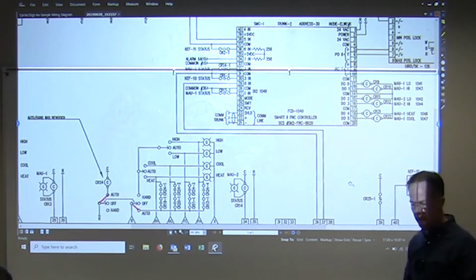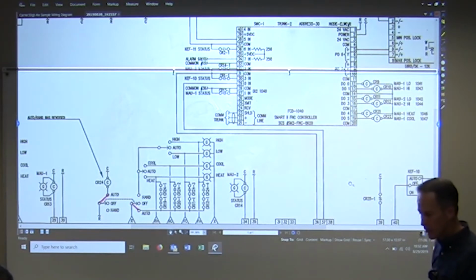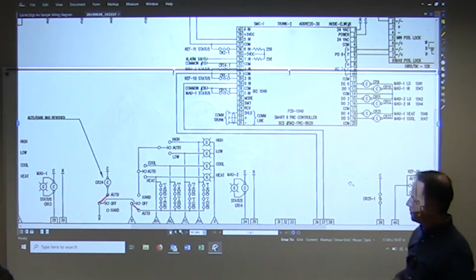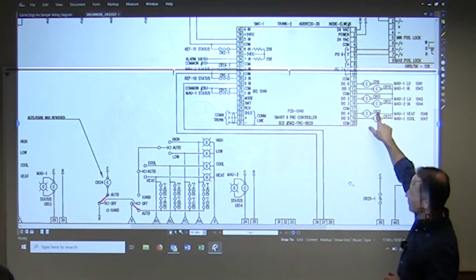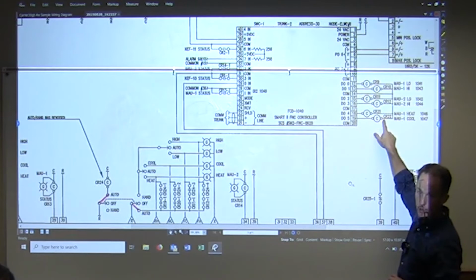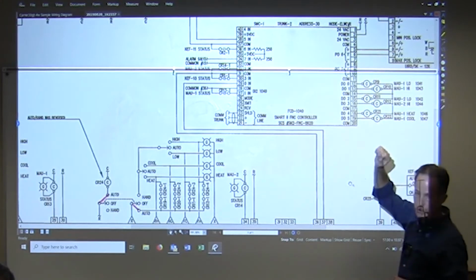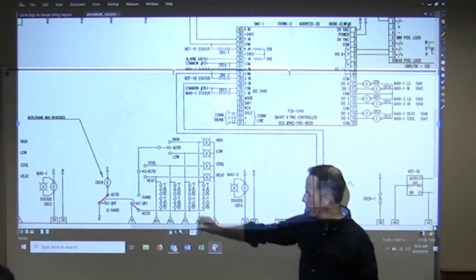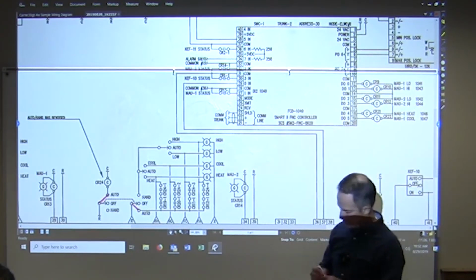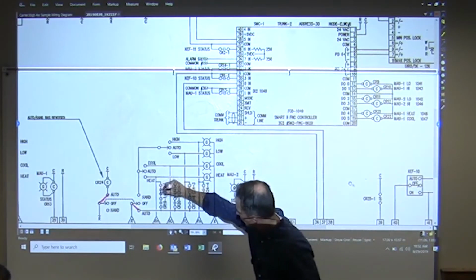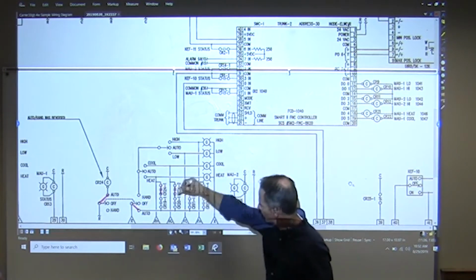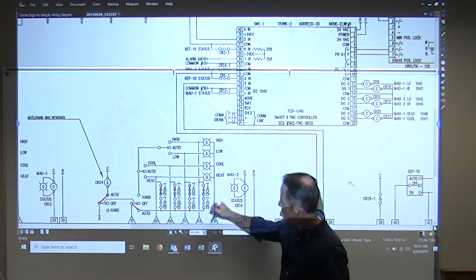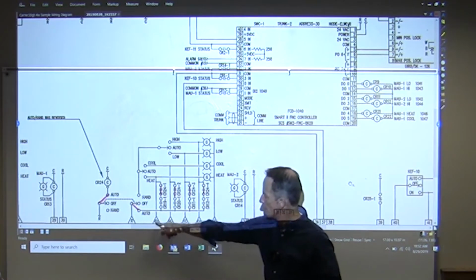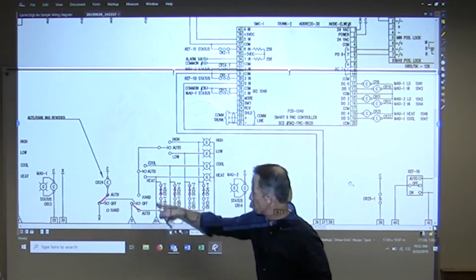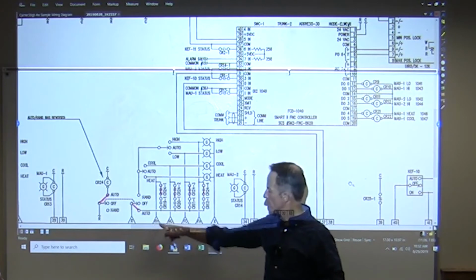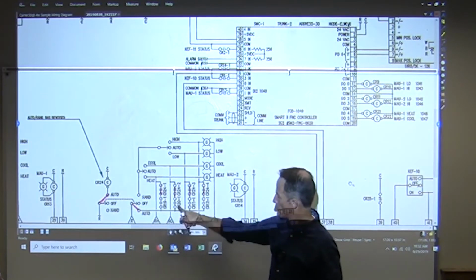I think the left exhaust fan 10, or makeup air unit 1. So let's say that this is 19 and 20 here instead of 21, 21. What happens when I energize CR19 and I'm in auto? Heat comes on. So this guy is made all the way through here because we're in auto, right? 19 gets energized. We turn, R comes up, goes through, and then drops back down. Same for cooling. If I do cooling with 20.